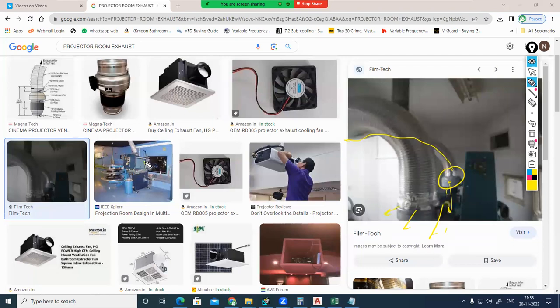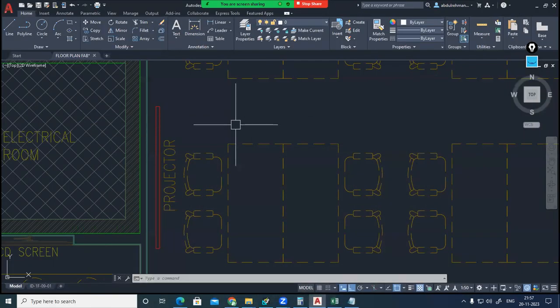Correct. Because the light rays the projector creates go to the front area only, meaning the theater area where people will be sitting. All the heat energy accumulated within it, the exhaust fan will take care of and expel to the outside. So the projector heat spreading to the surroundings will be negligible. Just 5 or 10% of the rated load, 5% maximum you can consider. But this is only for movie theaters, which have these exhaust systems. Conventional LED projectors will not have that much exhaust system. They have an exhaust fan, but it ejects the heat generated within the projector to the surrounding area only.